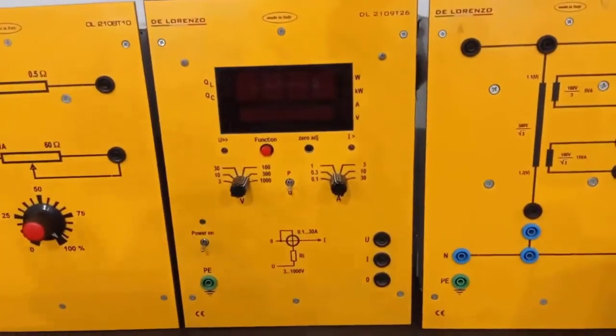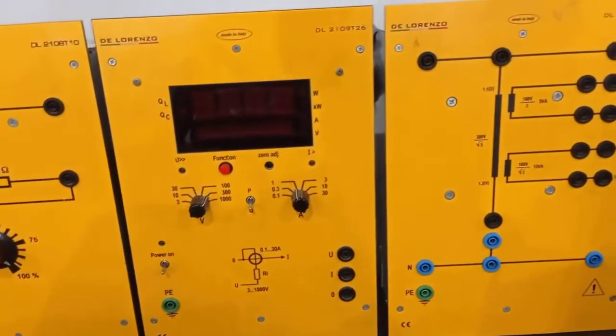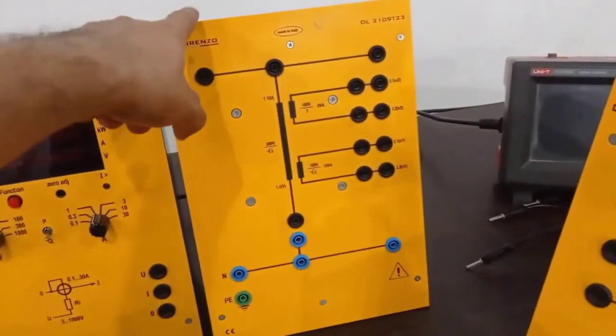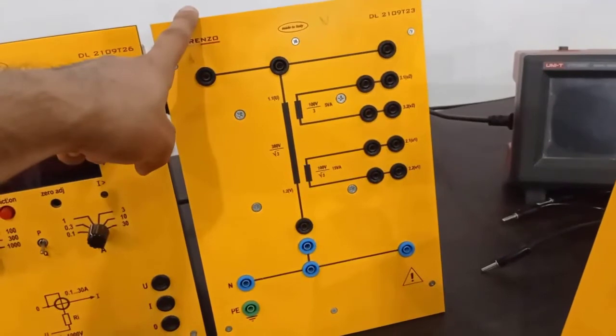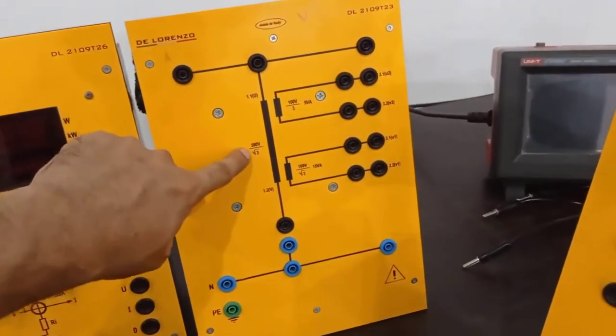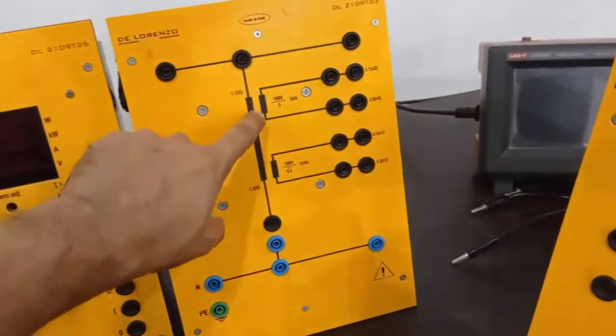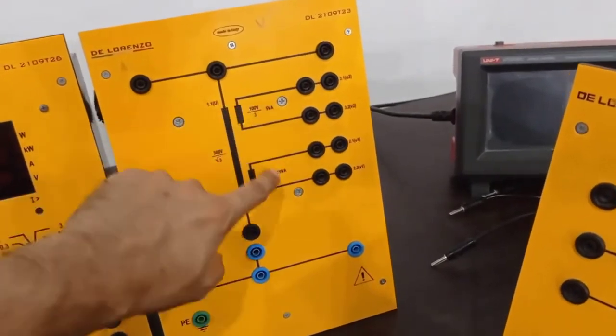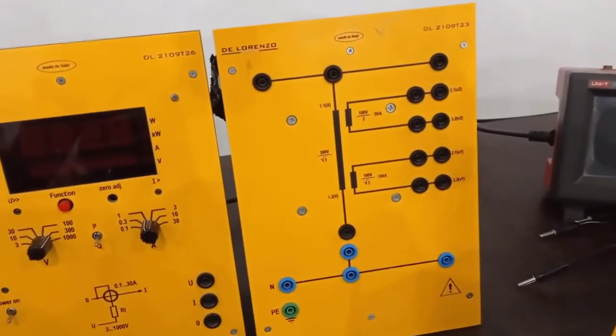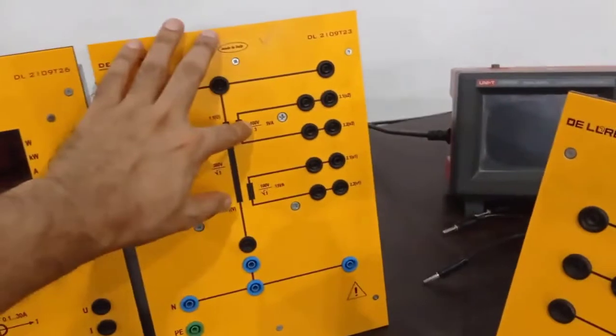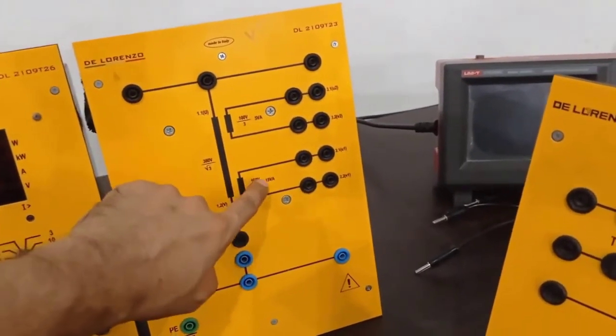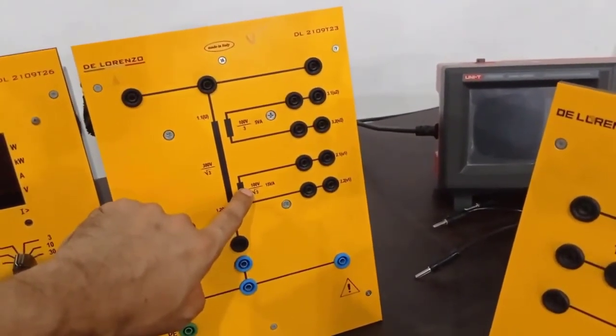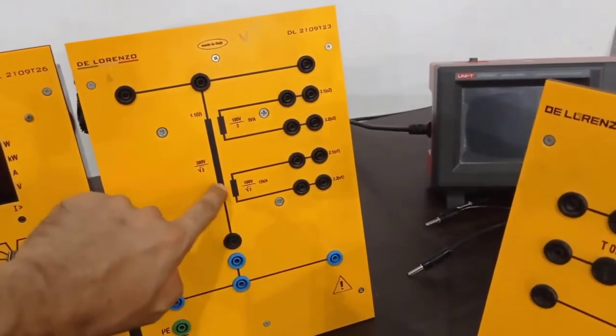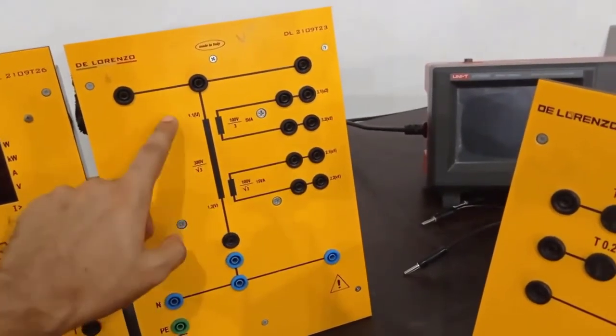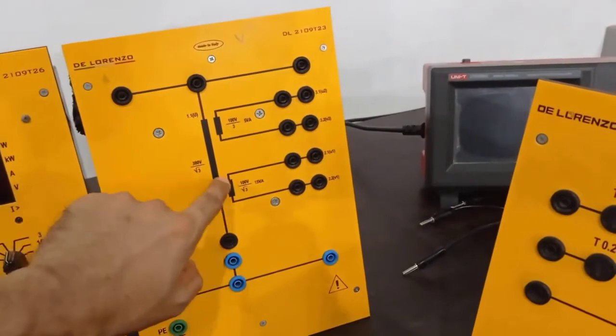For part B, in which you will study the steady state characteristics of the voltage transformer, here is a voltage transformer. Use its rating 380 over root 3 for the primary winding. This time there are multiple secondaries. In the CT we have a multi rating primary, here we have multi rating secondaries. Use this secondary which is rated at 100 over root 3. Root 3 will cancel out on both sides. We can write this rating as 380 by 100.